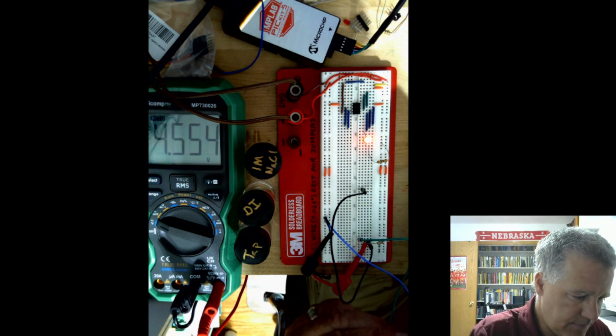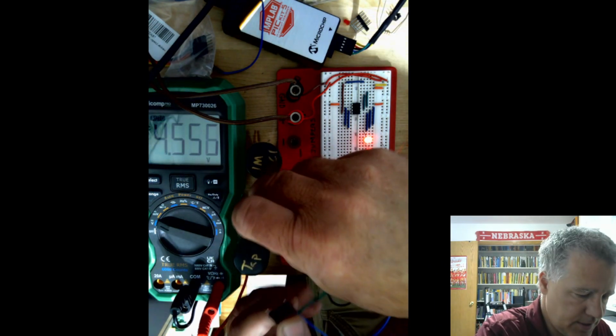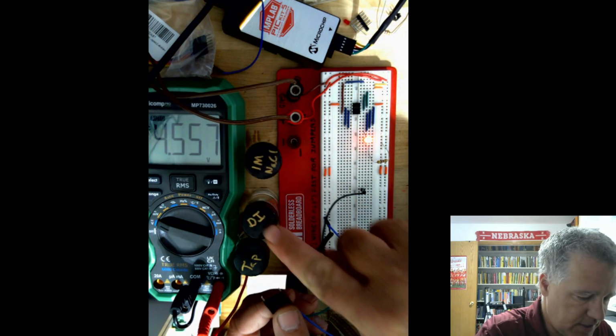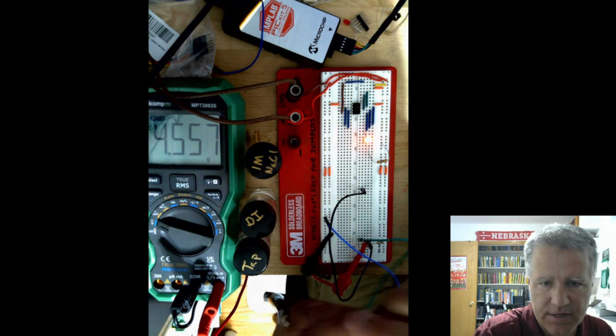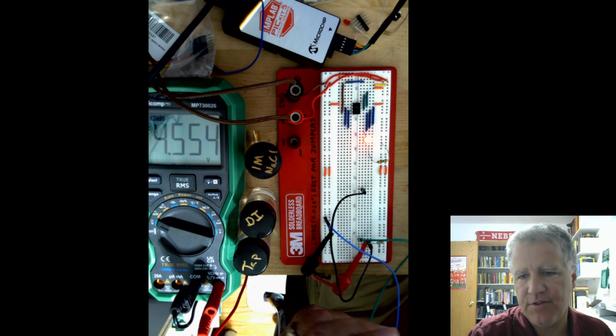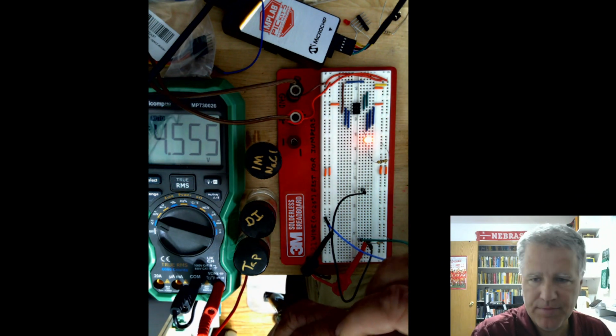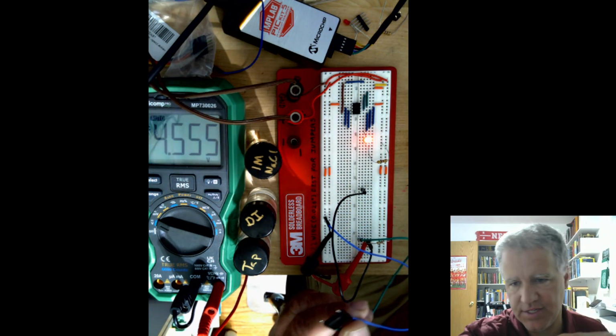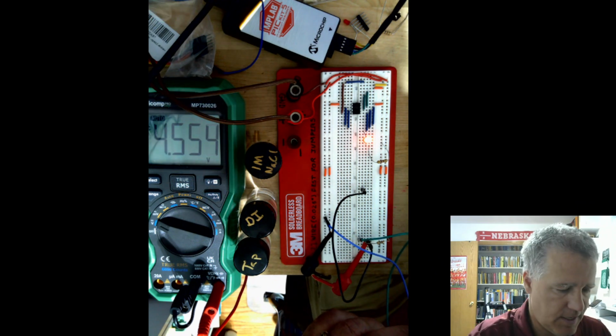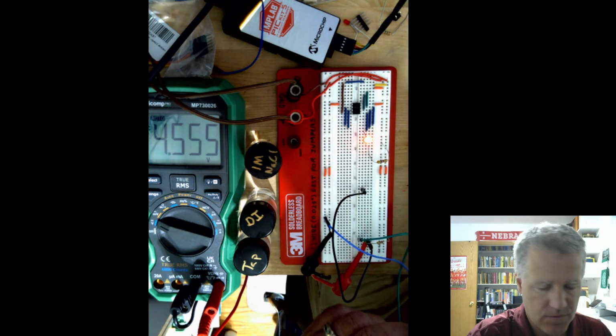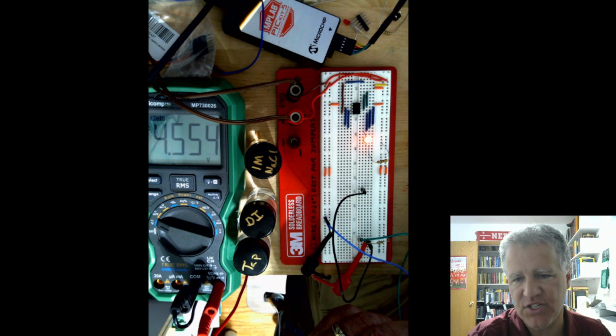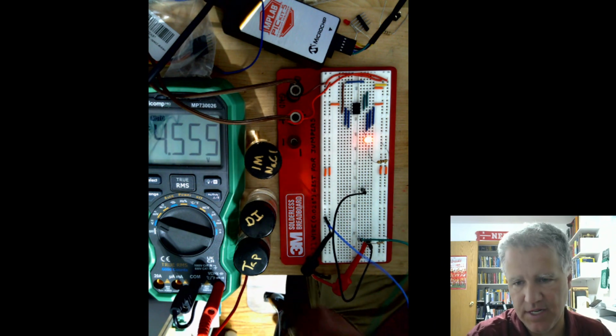And first, let's put this into the deionized water. So I've got deionized water, tap water, and sodium chloride. If you're doing this in sequence, probably best to go from the most dilute, the deionized, up to the most concentrated. Then we can pretty much just dry the probe and dip it in.